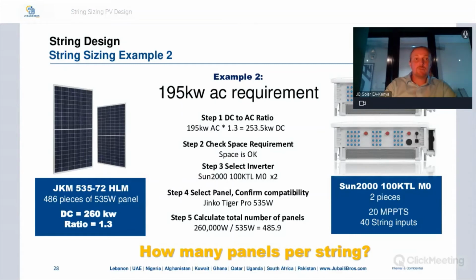So next example, we have a 195 kilowatt requirement, AC. Step 1 is the DC to AC ratio. The DC to AC ratio should be 1.3. So you take the AC and multiply by 1.3. 195 kilowatts AC times 1.3 equals 253.5. So that's our target for the DC.